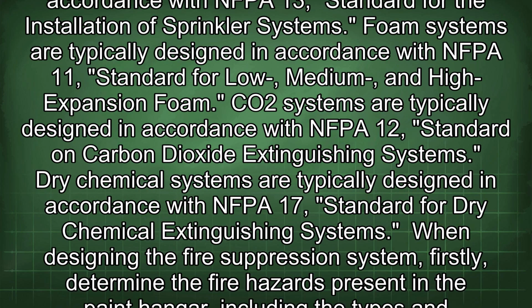Sprinkler systems are typically designed in accordance with NFPA 13, standard for the installation of sprinkler systems. Foam systems are typically designed in accordance with NFPA 11, standard for low, medium, and high expansion foam. CO2 systems are typically designed in accordance with NFPA 12, standard on carbon dioxide extinguishing systems. Dry chemical systems are typically designed in accordance with NFPA 17, standard for dry chemical extinguishing systems.